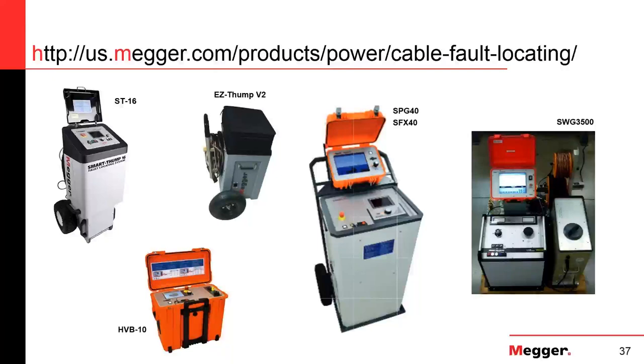On the very right, you have the SWG3500, which is an older but robust system. You have the three components separately. It also has the ICE method built in. And then in the middle you have the SPG40, which is considered the most sophisticated thumper you can have available in the North American market because it has all of the methods built in that we just talked about, including decay. It is a 40 kV system with 32 kV cap discharge, and the radar is on top. In this case, it's not fully integrated, the radar is separate. And then you have the high voltage bridge, which we're still making as a manufacturer, that applies the voltage drop method.